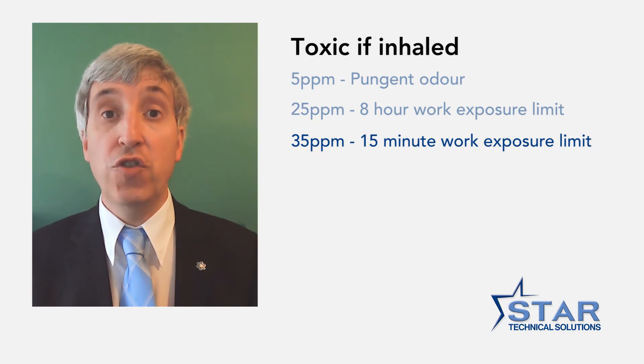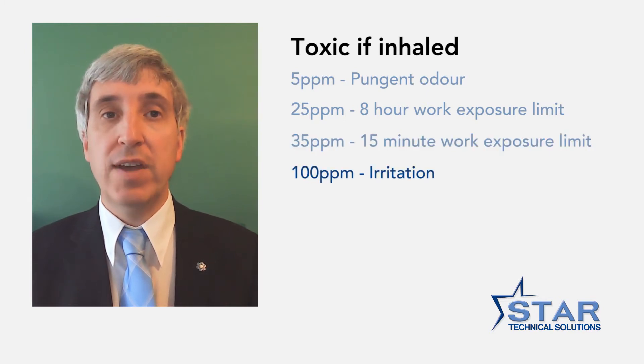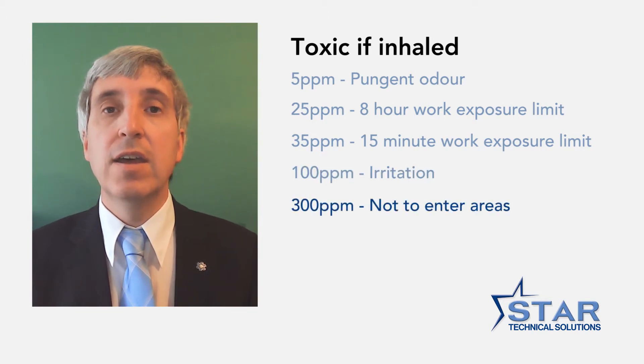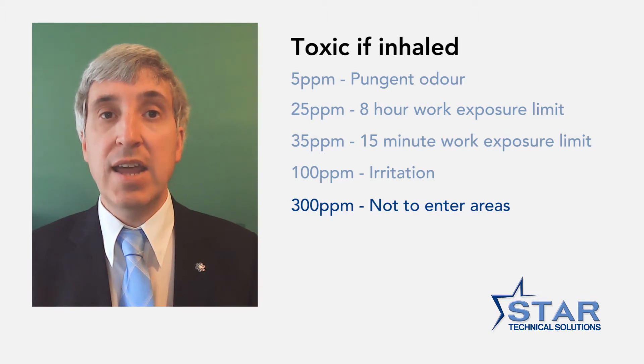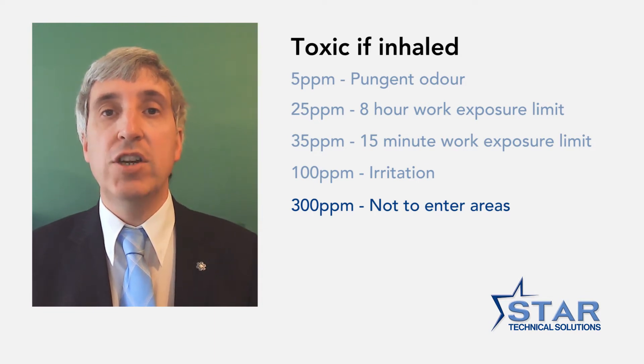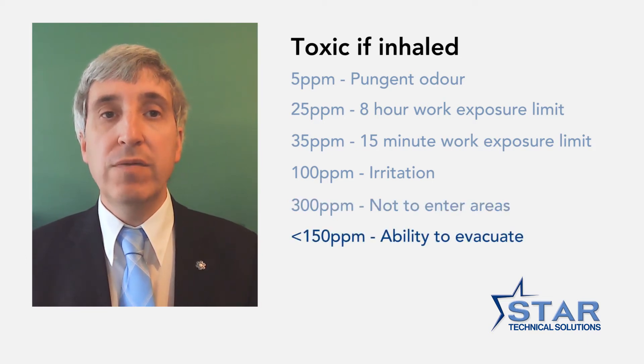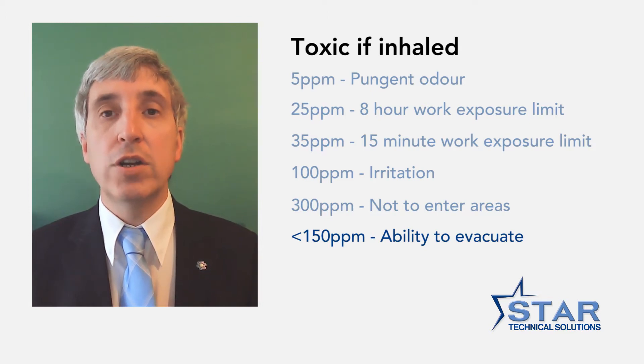At concentrations above 100 ppm, ammonia toxic effects can manifest with symptoms such as irritation to the eyes and mucous membranes. The National Institute of Occupational Safety and Health gives the IDLH for ammonia as 300 ppm for 30 minutes. The IDLH is the immediate danger to life and health and should be used for evacuation purposes only. The American Industrial Hygiene Association provides emergency response planning guidelines based on an individual's exposure to ammonia for one hour. Below 150 ppm, nearly all individuals exposed would not experience or develop irreversible or other serious health effects that could impair their ability to escape or to take preventive action.